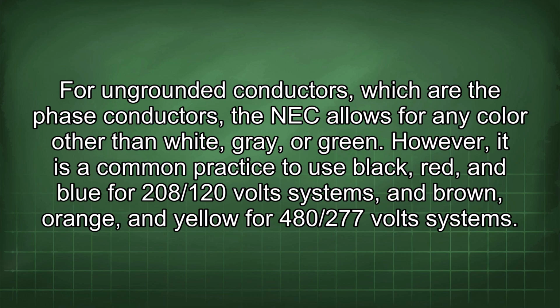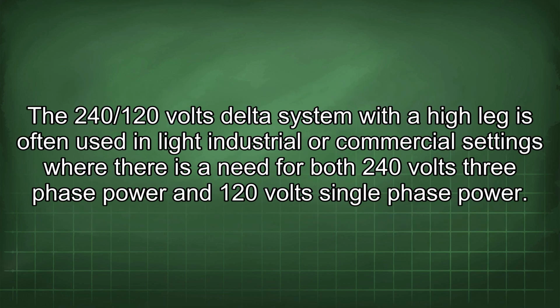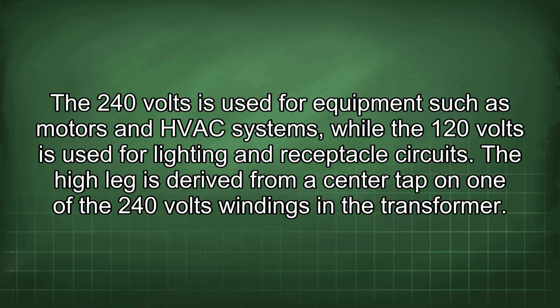However, it is a common practice to use black, red, and blue for 208/120 volt systems, and brown, orange, and yellow for 480/277 volt systems. The 240/120 volts delta system with a high leg is often used in light industrial or commercial settings where there is a need for both 240 volts 3-phase power and 120 volts single-phase power.